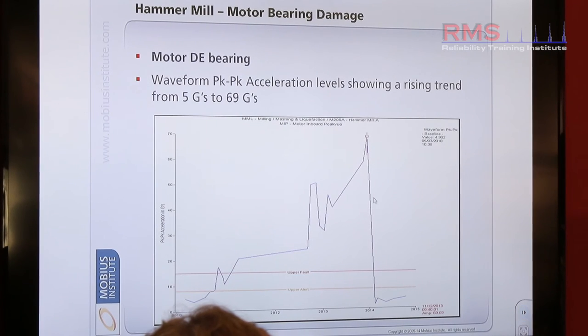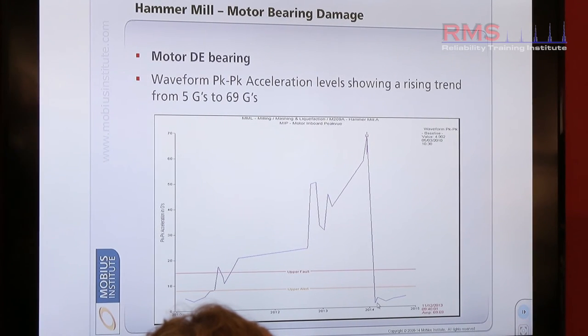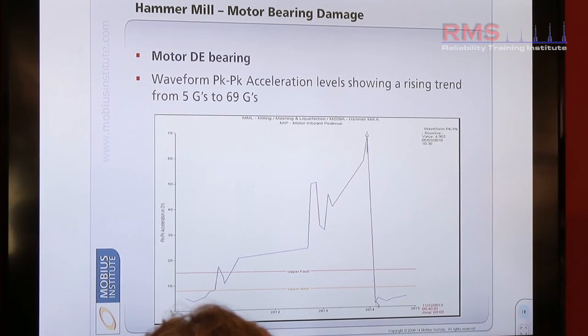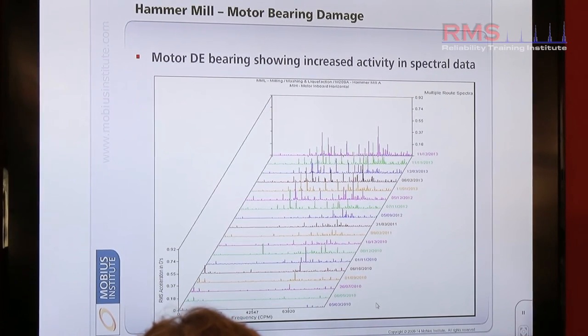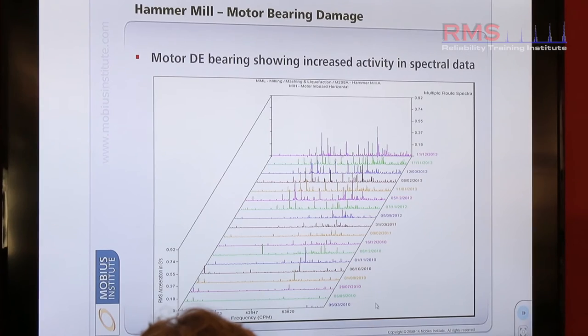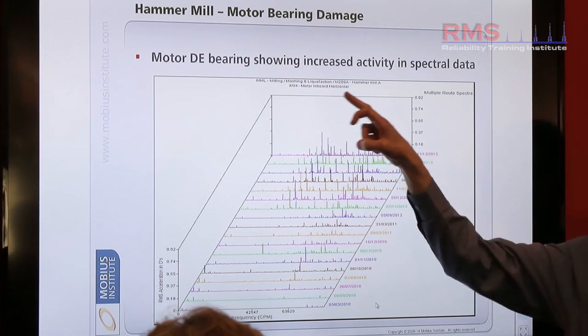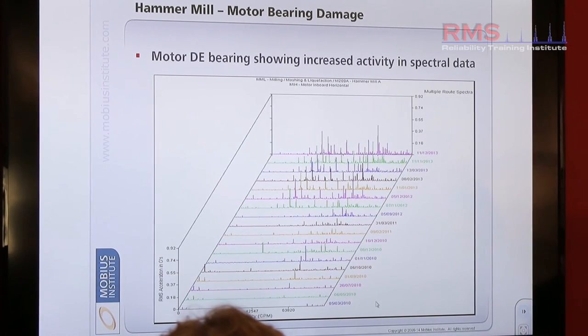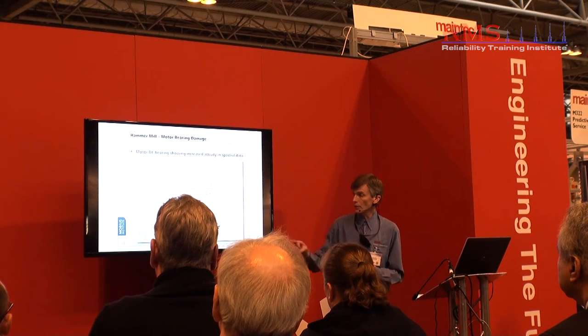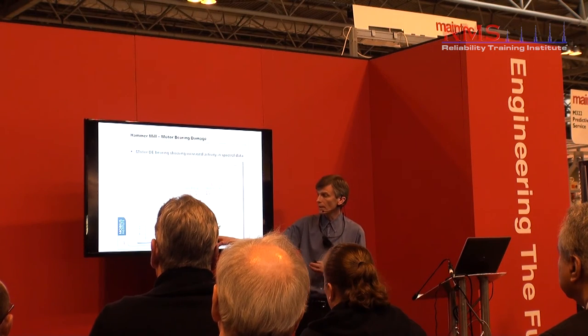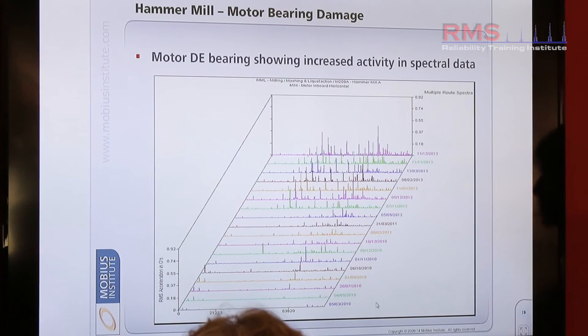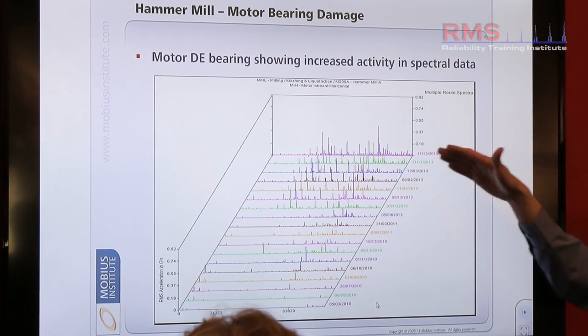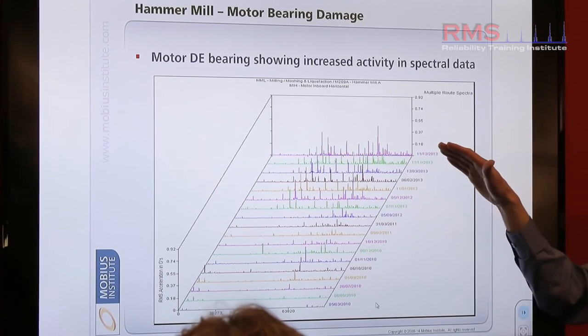And then you can see after repair that the levels returned to normal afterwards. This is the frequency heartbeat of a particular point on the machine — the motor drive end or motor inboard bearing. So this is the bearing at the motor drive end. And you can see the heartbeat month on month — the most recent reading back when the problem was present, how the heartbeat has changed.